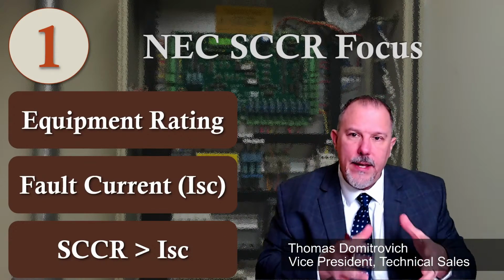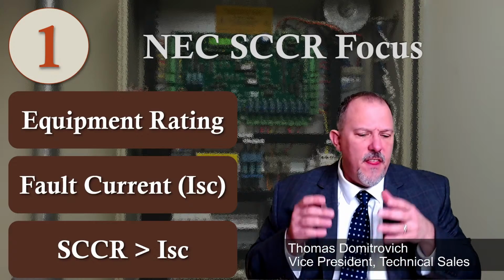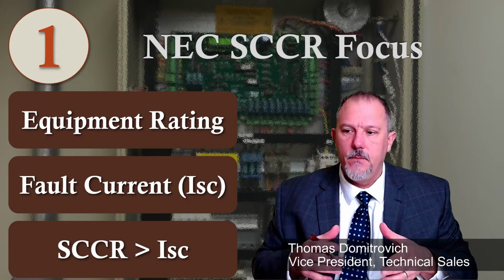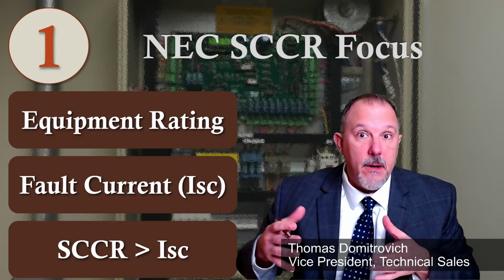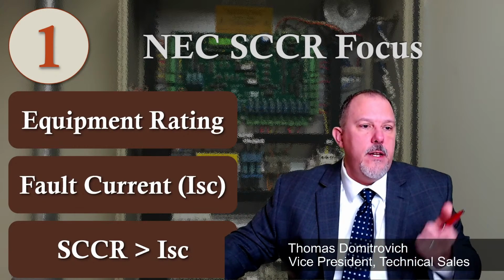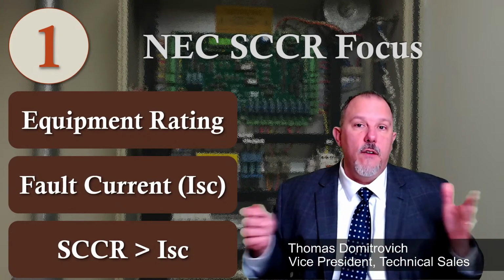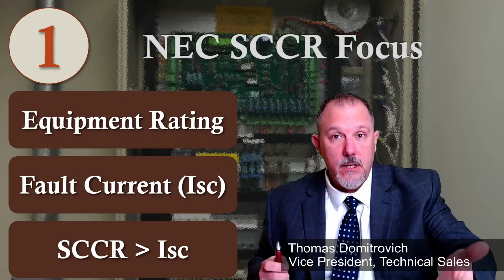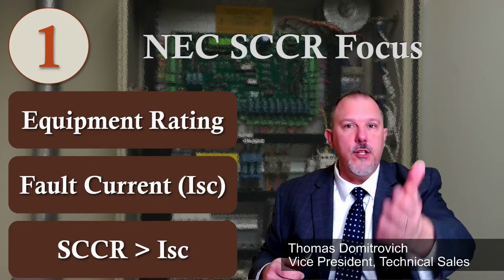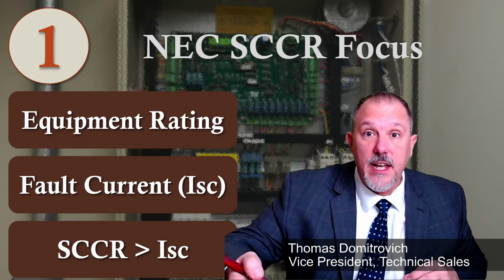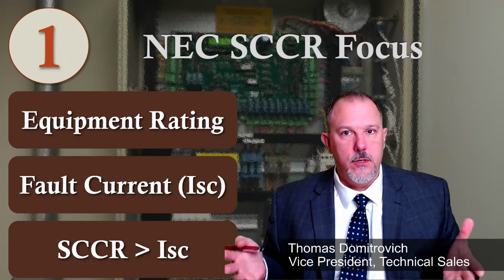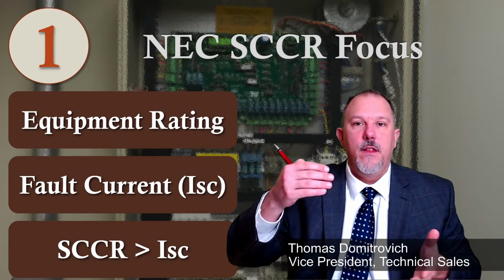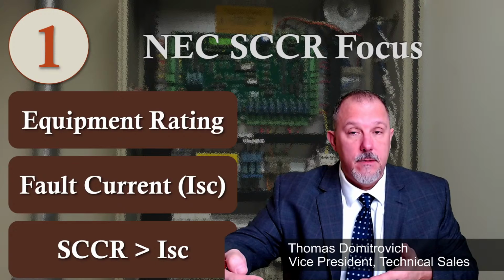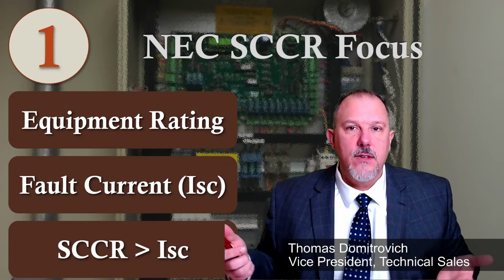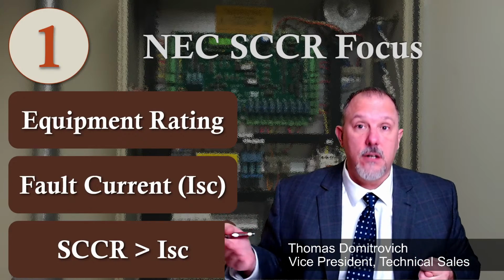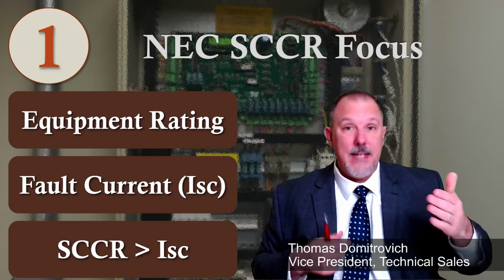And this is where the OEM, the manufacturer, comes into play. Think about a circuit breaker. Circuit breakers interrupt various levels of fault current depending upon the voltage, right? Not one circuit breaker can interrupt all fault currents. What do we sell? We sell a 10K breaker. We sell 22K breakers. We sell 42K breakers. We sell 65K breakers, 100K circuit breakers. So we have options for customers so that they can select the circuit breaker with the interrupting rating that meets their needs. If they only have 4,000 amps available fault current, they don't need a 65K circuit breaker. You're going to pay more for a 65K circuit breaker than you will for a 10K circuit breaker.